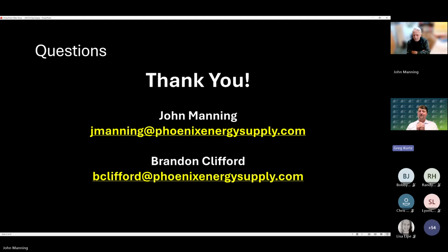All right. I see another question from Rick. He's asking about flushing speeds. John, does the program give you anything on that? Yes, under the loop field, once you get all the parameters set in your loop field, scroll down to the bottom of that tab, and it'll tell you exactly the flow rate and expected pressure drop of what the flushing requirements are to achieve that 2 feet per second that we all like to see. I always like to push it above that 2 feet per second, but it does give you that minimum purging flow requirement based on all the geometry you've put into the loop field piping.